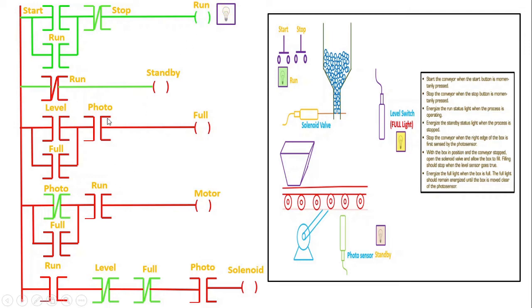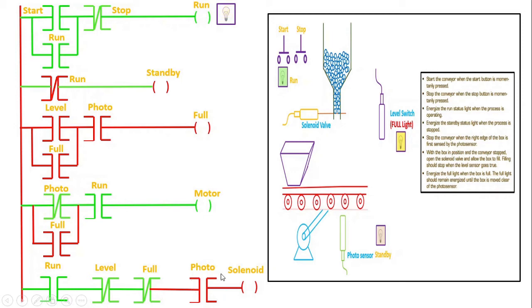Once run is energized, checking again — run is present, so that contact is energized. Because photo was already in normally closed position, the motor rung gets energized and the motor starts rotating. Another contact of run, using the same address, also gets energized. The conveyor starts moving, the box starts moving, and it comes to the position as indicated in the animation. Once it reaches that point, the photosensor senses it and goes high — the photosensor gets activated.